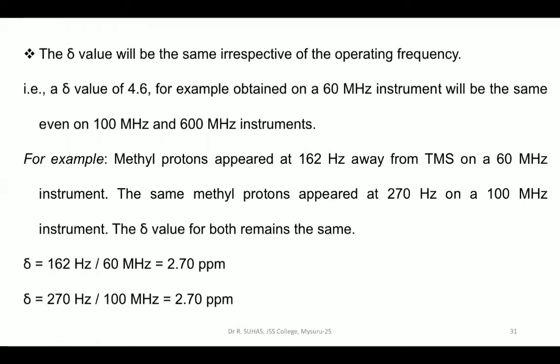At what operating frequency should NMR be run? There is no standard value — you can have 60, 100, 300, 400, 500, or 600 MHz. You must always remember that the chemical shift value remains the same irrespective of the instrument used. A delta value of 4.6 PPM obtained on a 60 MHz instrument will be the same even on a 600 MHz instrument.